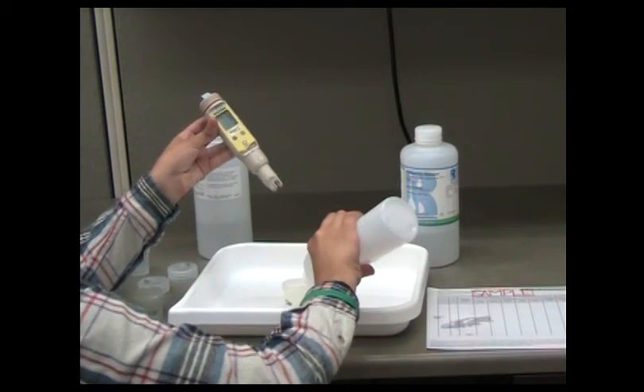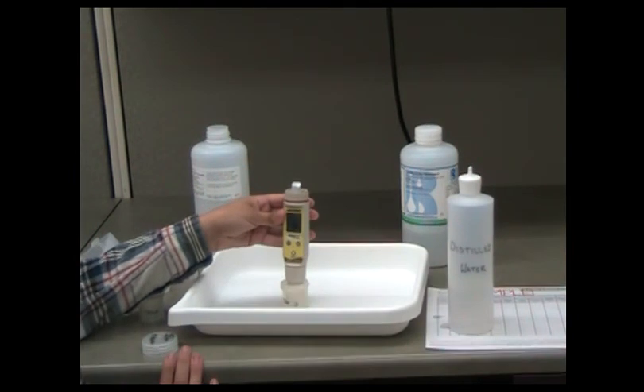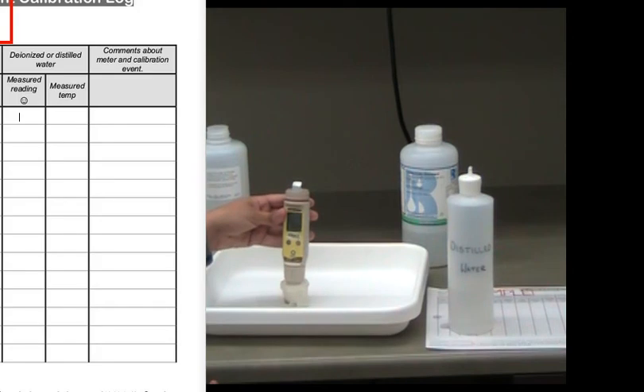Submerge the probe a fourth time in the 30-milliliter jar of distilled water. Allow the reading to stabilize. Record the measured specific conductance reading under the distilled or deionized water section on the calibration log.